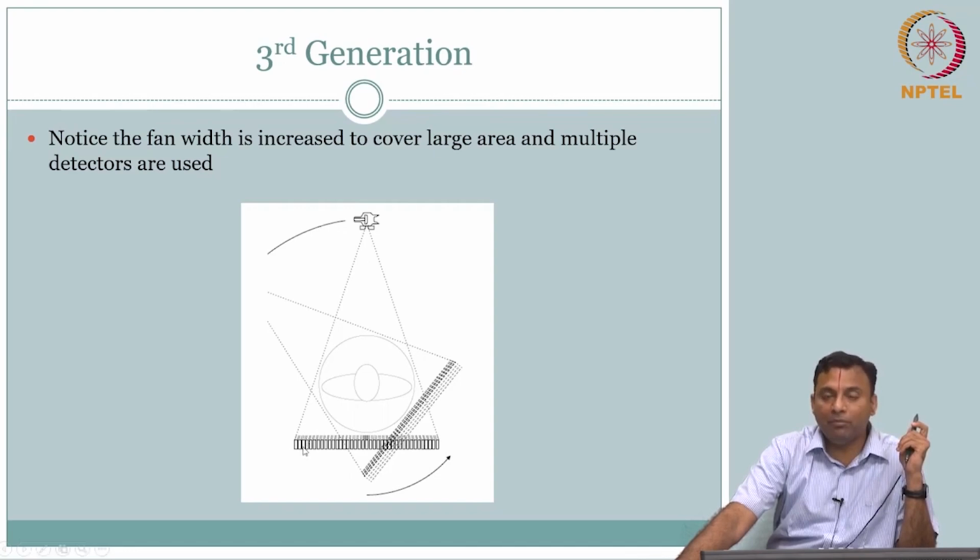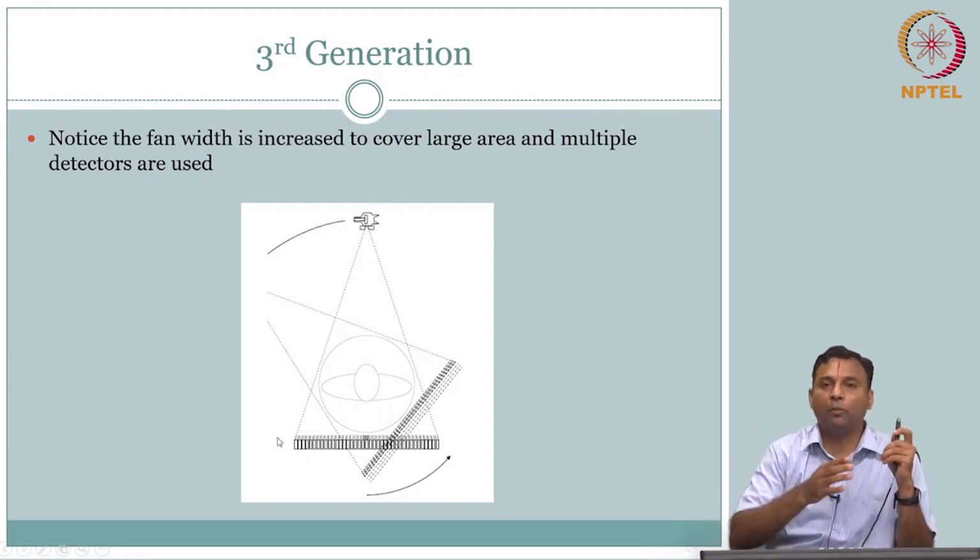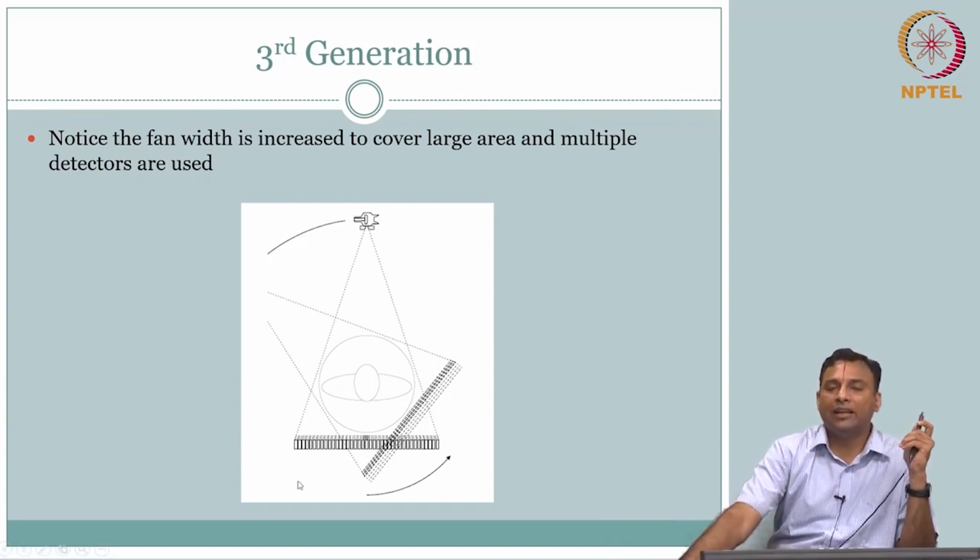Adding to it, the element size is now small and you are packing many elements, so the detector efficiency also goes down slightly. Everything said and done, you get a significant reduction in time, but you have really increased the cost, and to get the same quality as your earlier generations, you have to increase the exposure slightly.